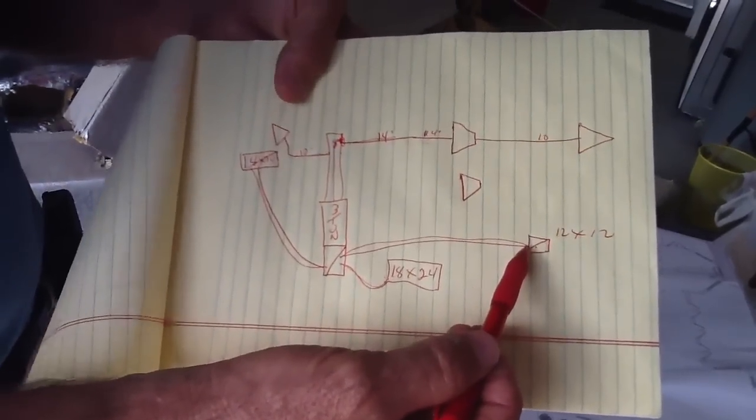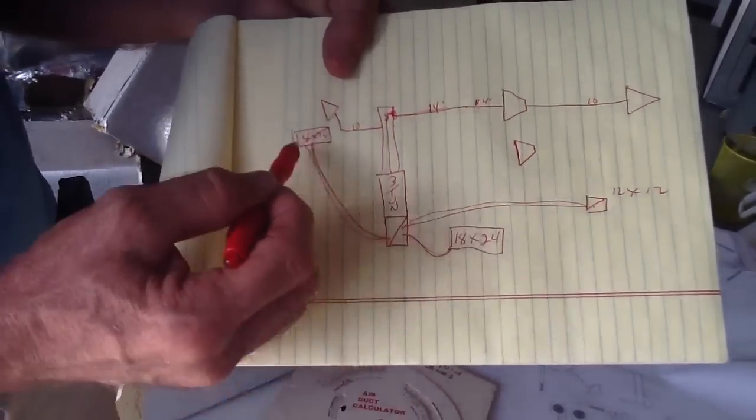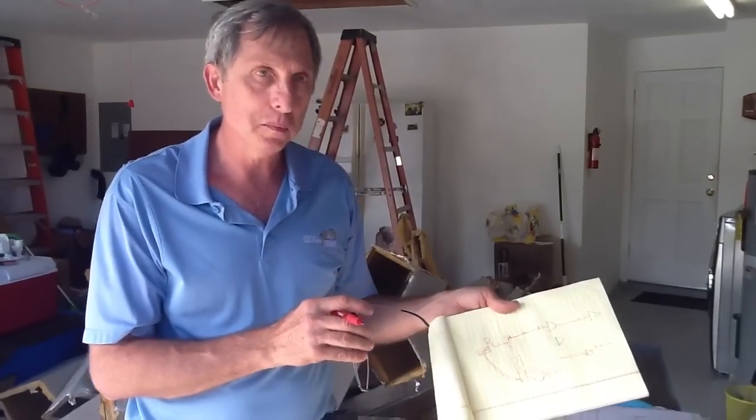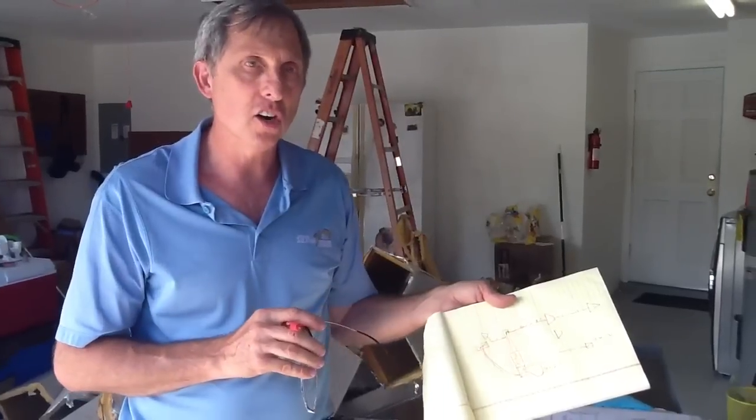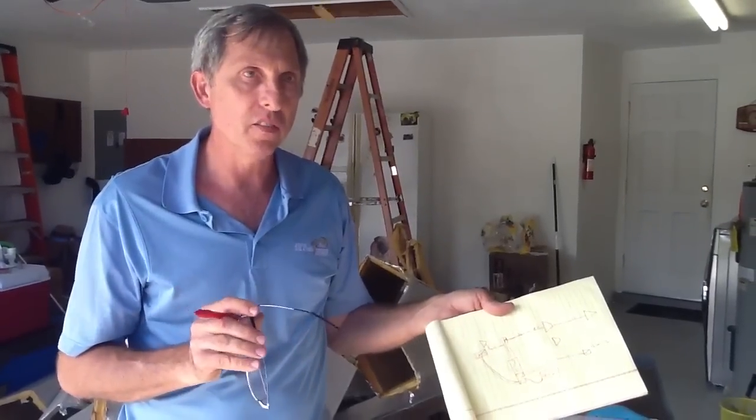This is in order to make sure you have the correct static pressure. Guys, get in the habit of always taking your returns back to your plenums. If you don't, you're going to live to regret it. This is just a quick, basic rundown of how to kind of place the ductwork into a trunk system. This is how to place the returns in the return plenum individually.